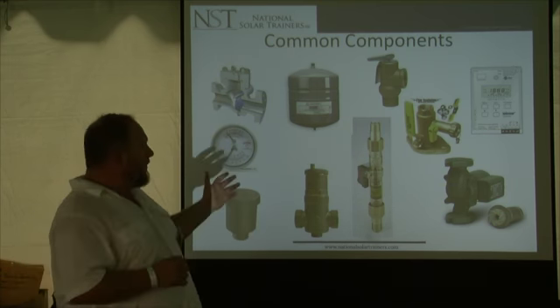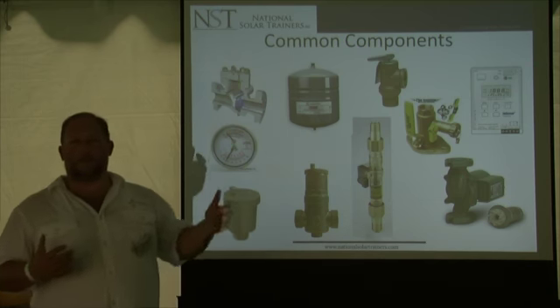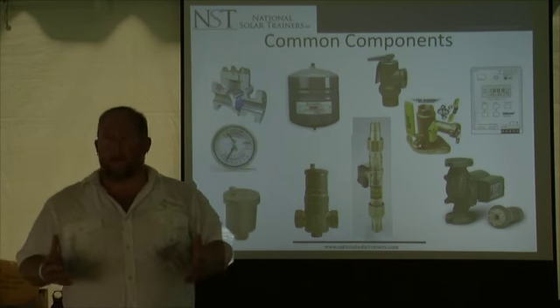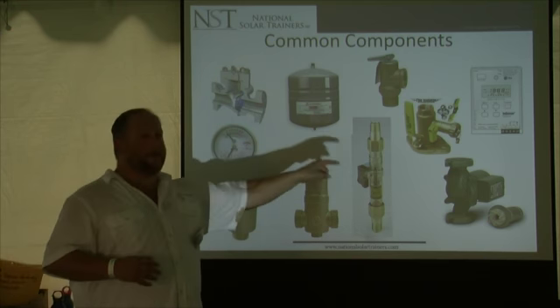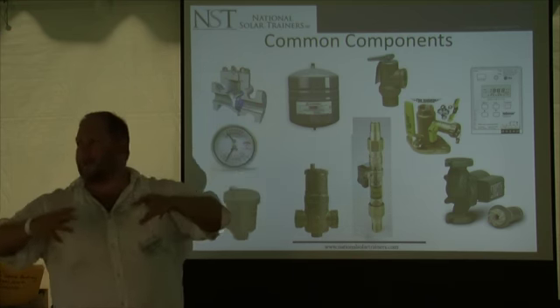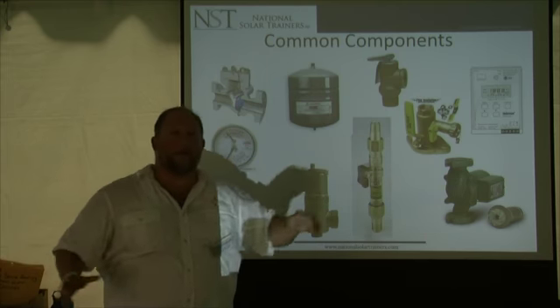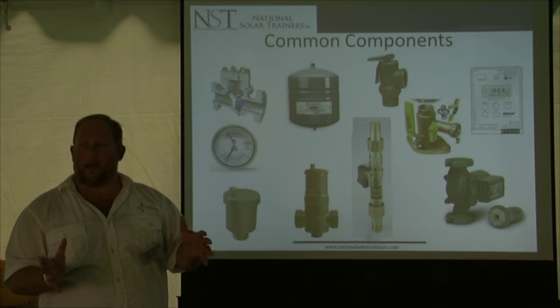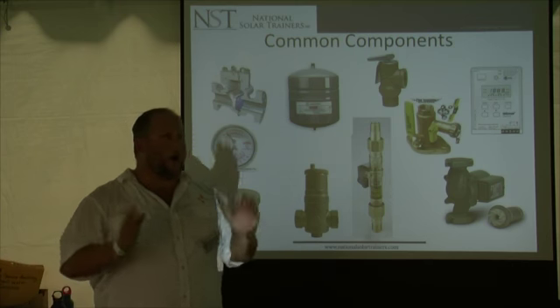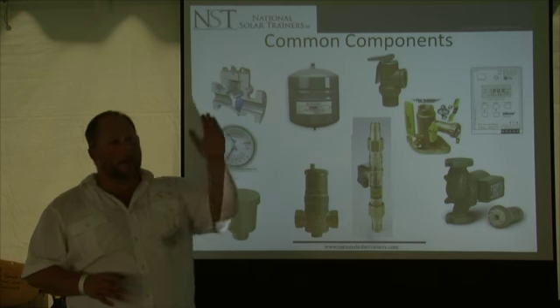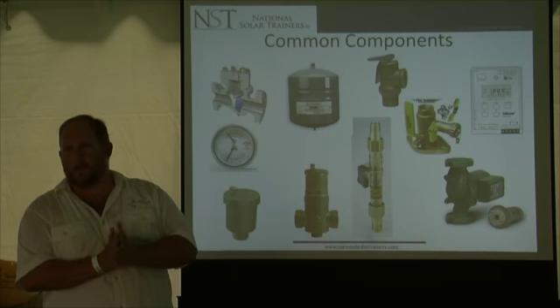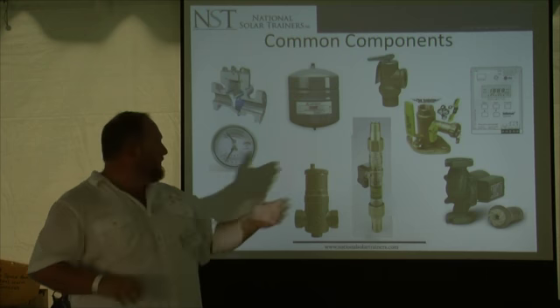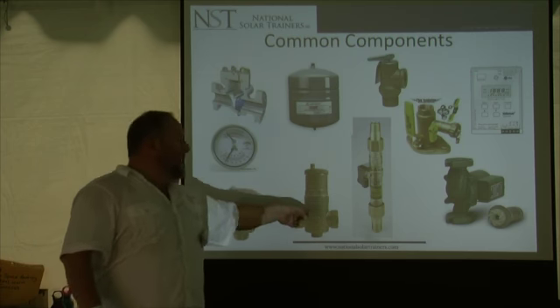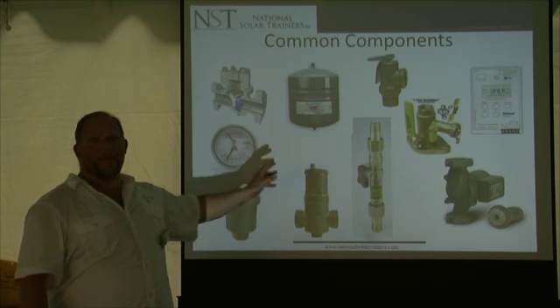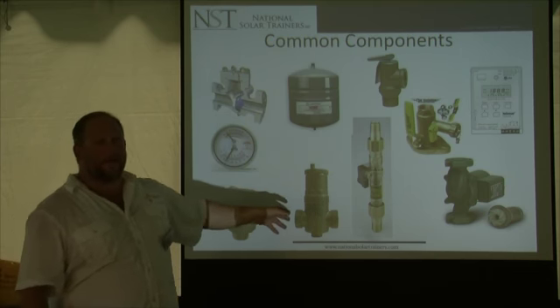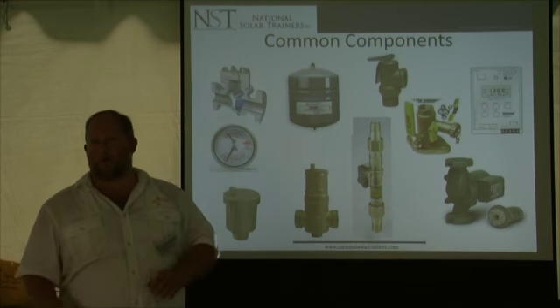So one nice thing over the last several years: guys were just buying this piece and that piece and that piece, and they were putting them together down in their basement. And now you see these nice little compact pump stations that include all of the pieces that you need. And again, there's a pump station down there that you can take a look at. You've got flow meters. This is actually the most important piece, the air vent, because if you don't get the air out of the system, it's going to cause the pump to overheat.